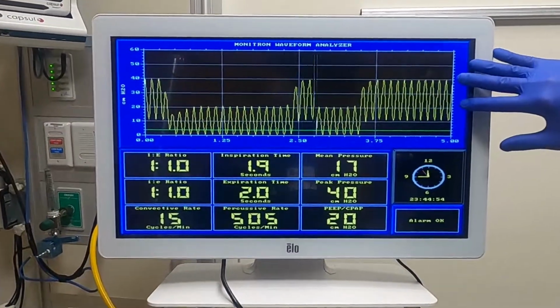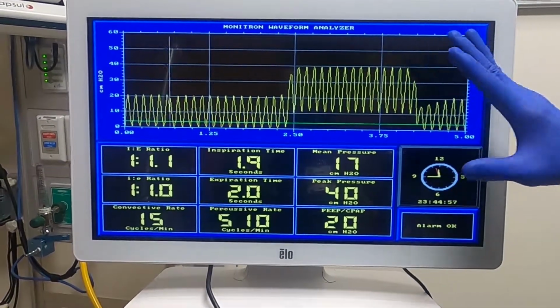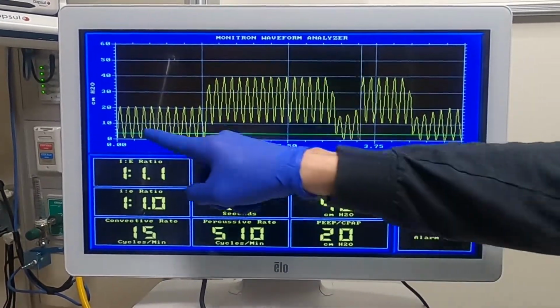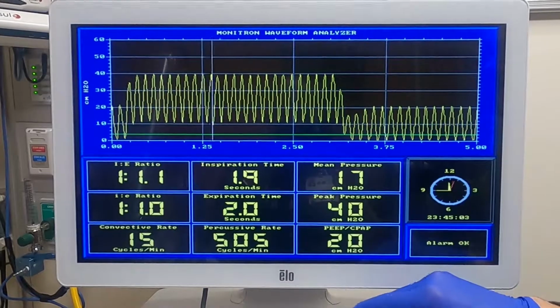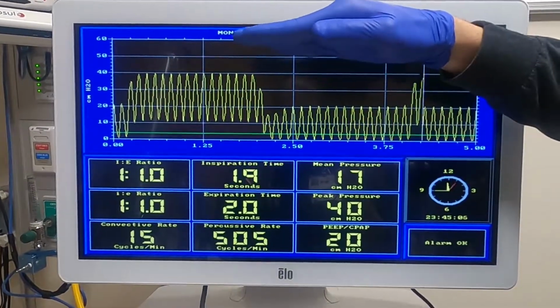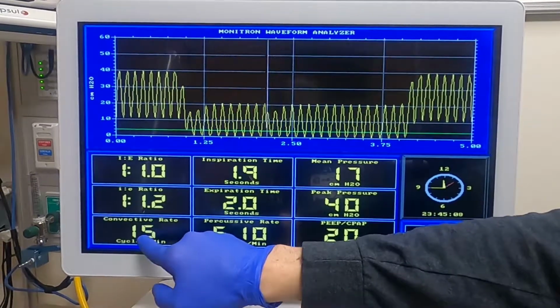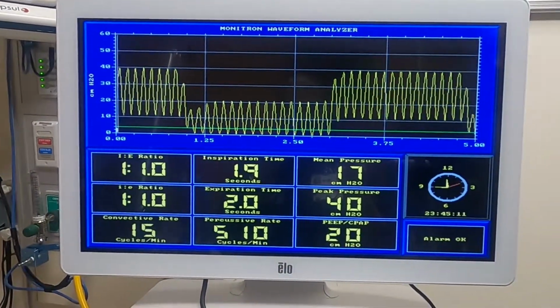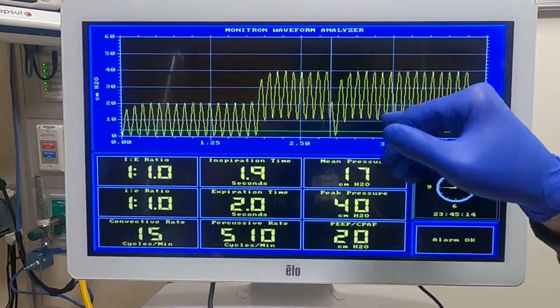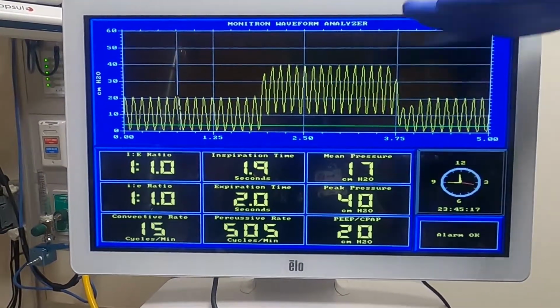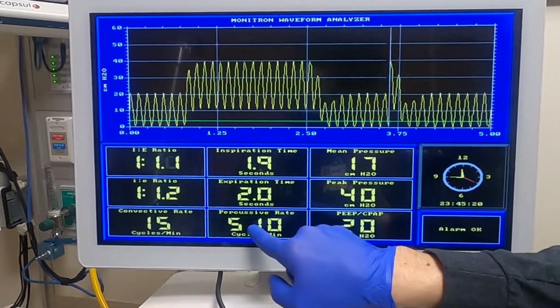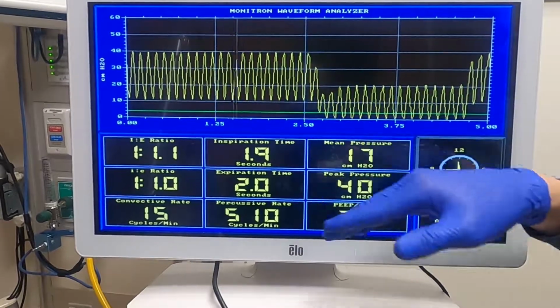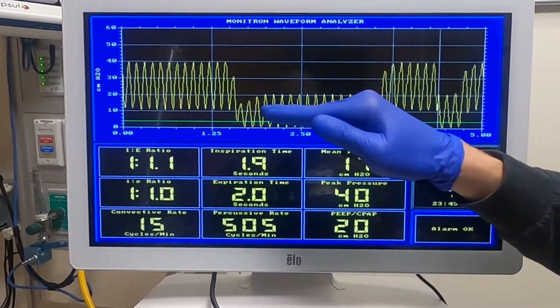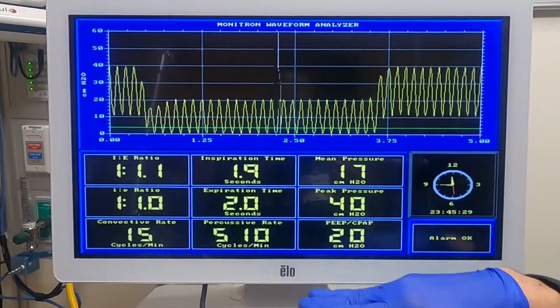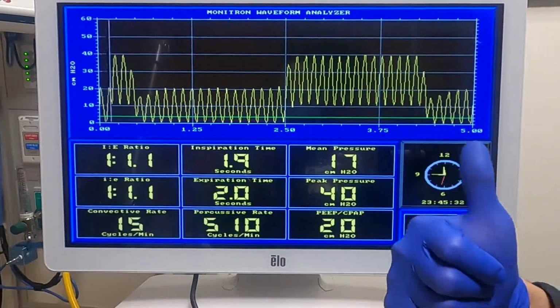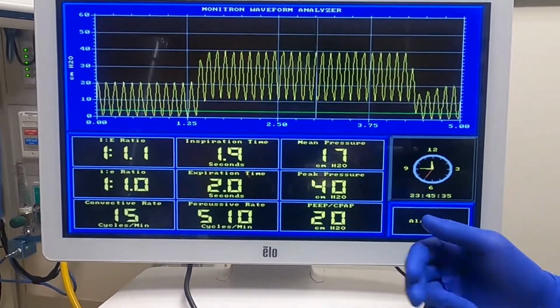Here is our waveform. And as you can see, this really illustrates the benefit of this machine. You have your high frequency ventilation pulses in combination with your really large volume conventional ventilator type breaths. Here we have it set at a rate of 15, so 15 times a minute you're going to see these big breaths. This is the big volume where the chest is going to rise. And then 500 times a minute, you're having these small vibrations. So even during the expiratory phase of the patient down here, you're still going to see their chest vibrating. All of that is for secretion removal, CO2 removal, and oxygenation.